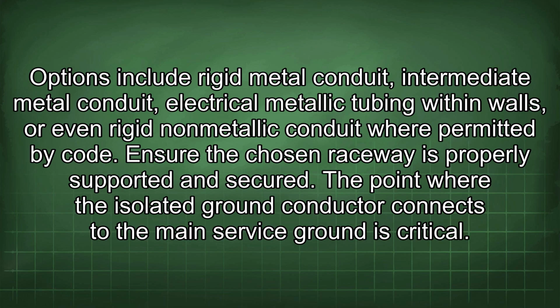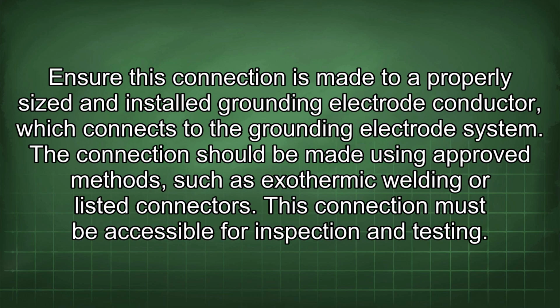The point where the isolated ground conductor connects to the main service ground is critical. Ensure this connection is made to a properly sized and installed grounding electrode conductor, which connects to the grounding electrode system. The connection should be made using approved methods such as exothermic welding or listed connectors. This connection must be accessible for inspection and testing.